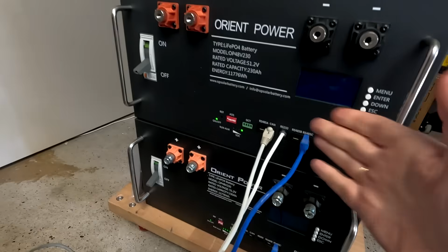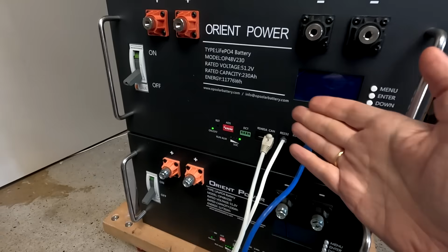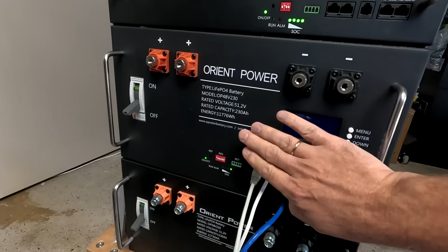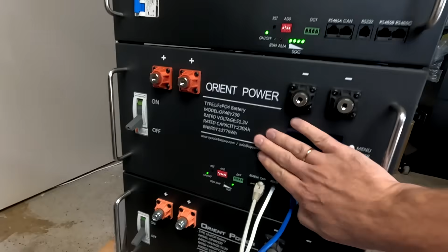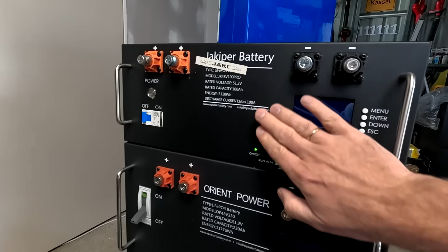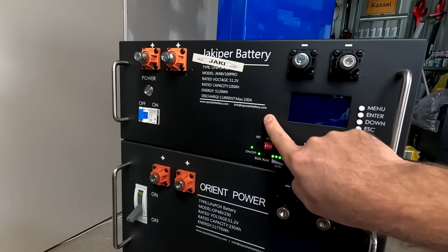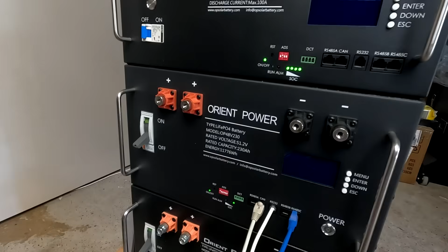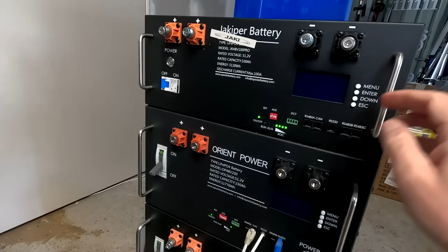So my biggest concern is that the information the master BMS gets from the slave batteries is not correct, or it's not actually factoring in the data. It only sees a second battery and assumes it is the same size as itself. Yeah, when we set this one here, for example, for 100 amp of charge current, it automatically assumes the other battery connected to it takes another 100 amps as well. But this is a smaller battery. This has only 100 ampere hours and this is a 230. So if I have a charge current of 100 amps here and only 50 amps here, it still allows the inverter to charge with 200 amps.